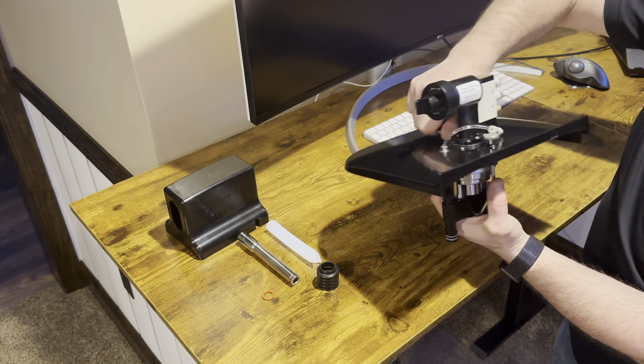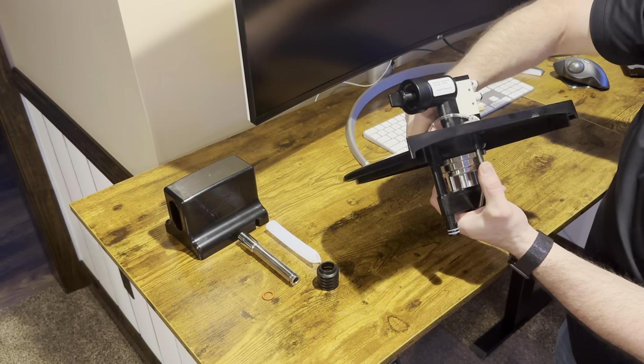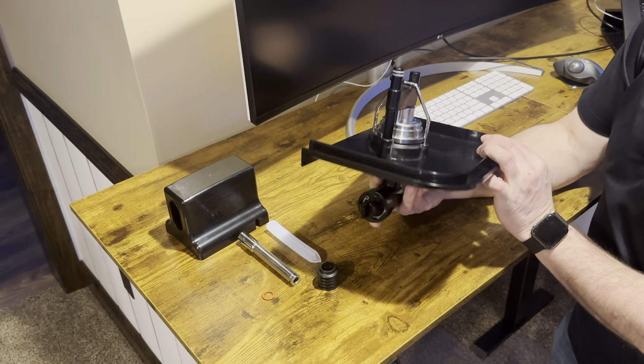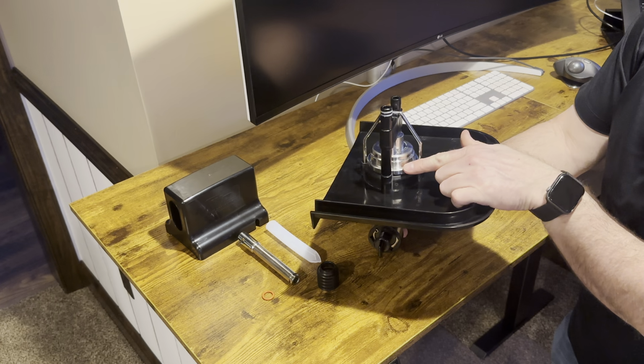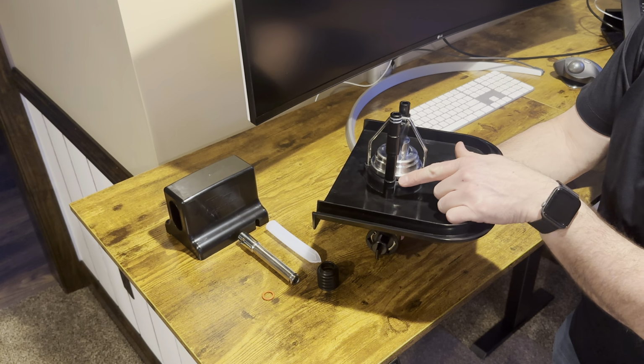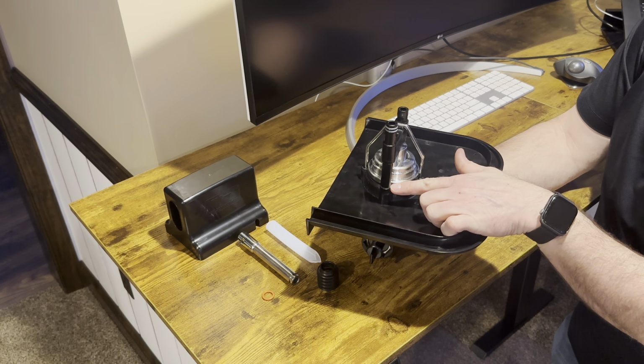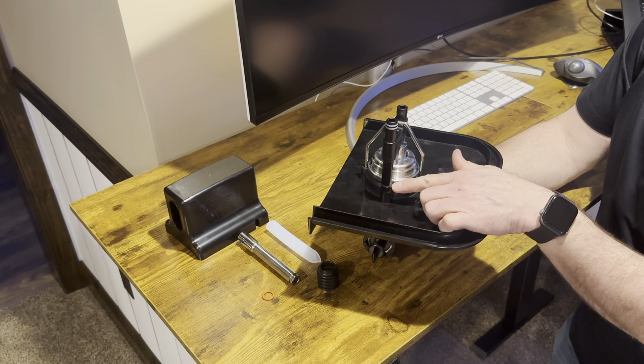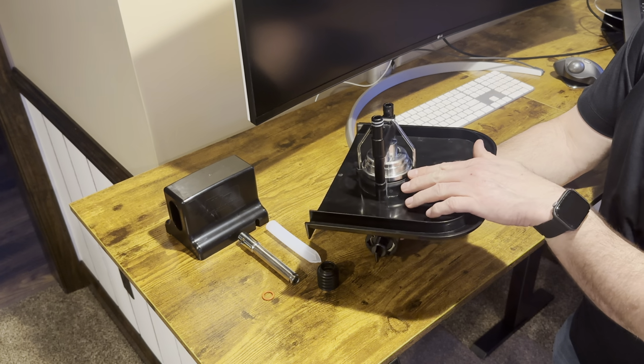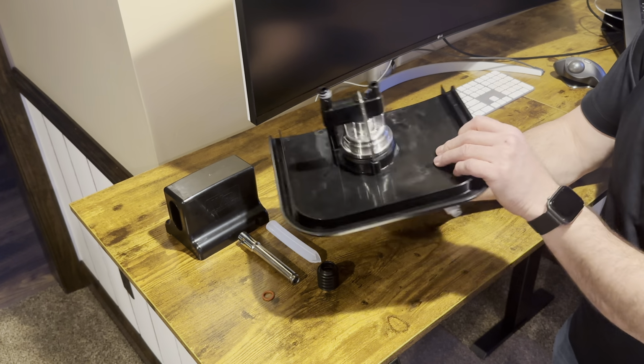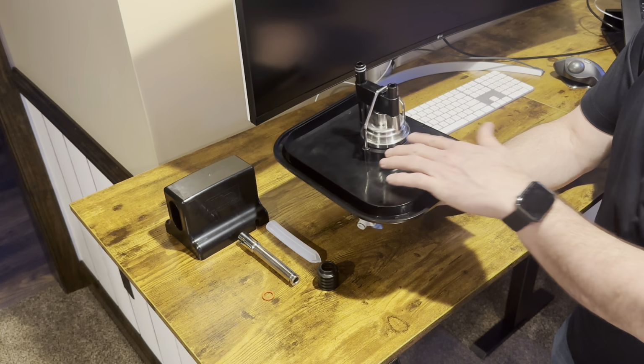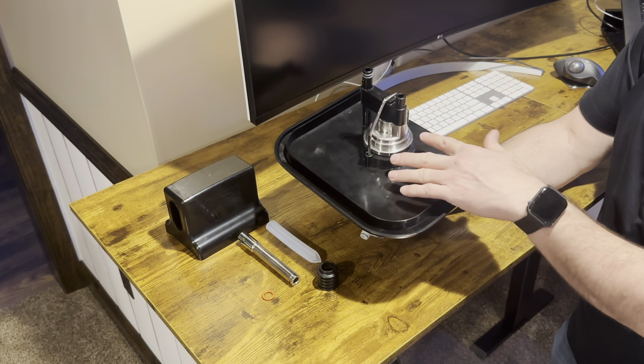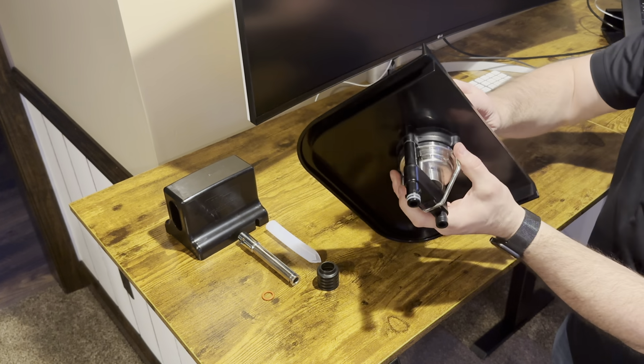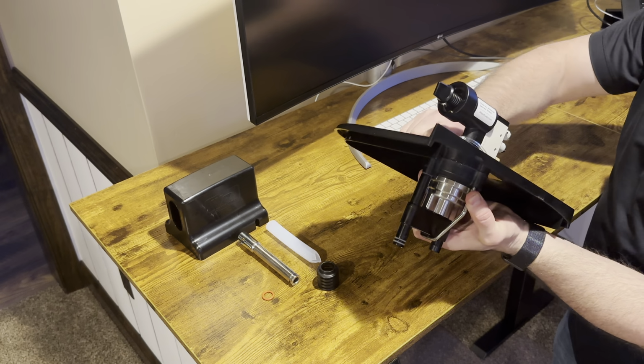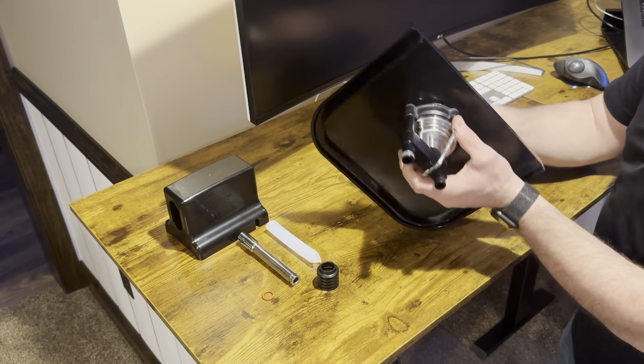And once that's drawn down, if you look on the bottom here, there's a little notch in the pump head right here that should be sitting against the black plastic pump body when it's drawn down the whole way. And just look at this groove, make sure things seem like it came down nice and square. Give them a little twist yet, snug them up.